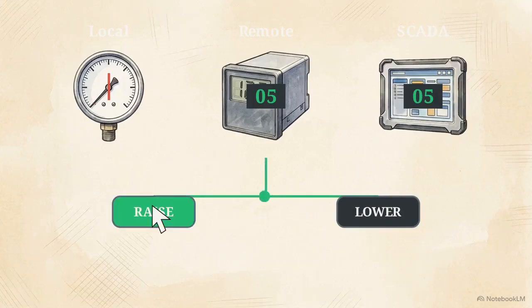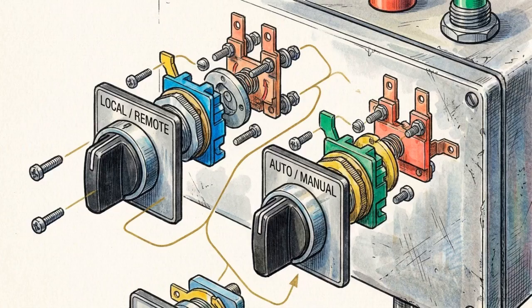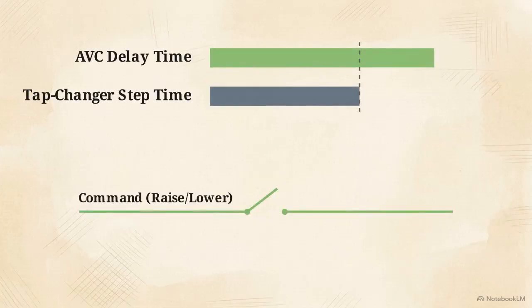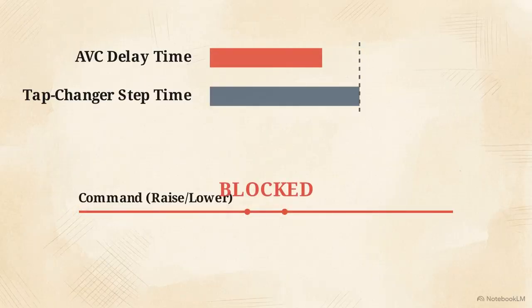Next, we test the logic interlocks by initiating raise and lower commands. You must test these commands across all permutations of the local remote and auto manual selector switches to verify they only execute in their intended modes. During these tests, confirm that command paths are blocked if the automatic voltage control delay time is set shorter than the tap changer step time.